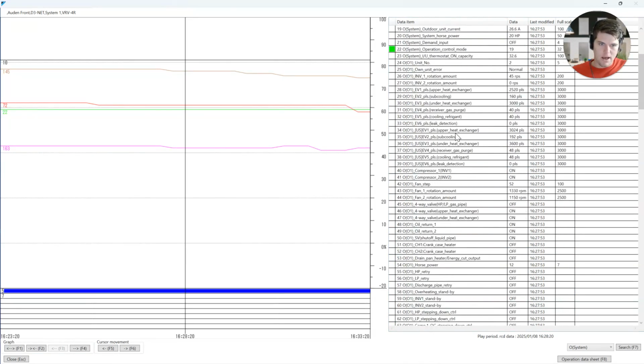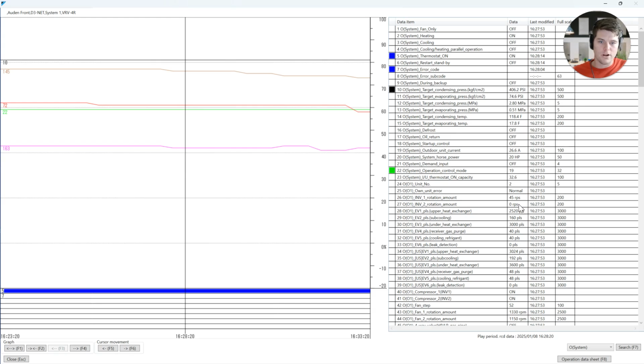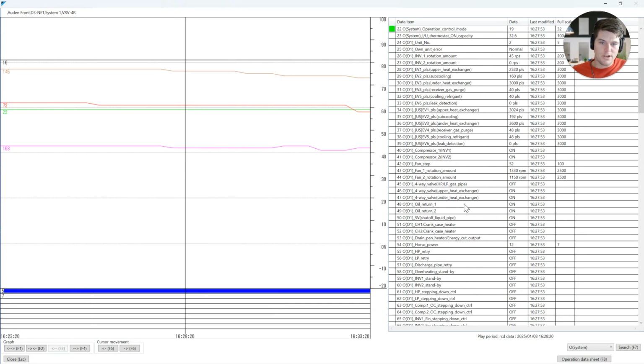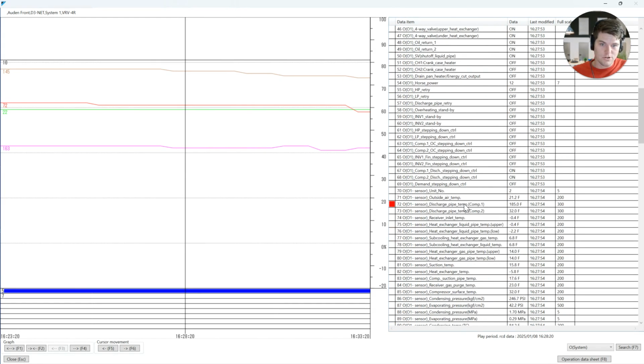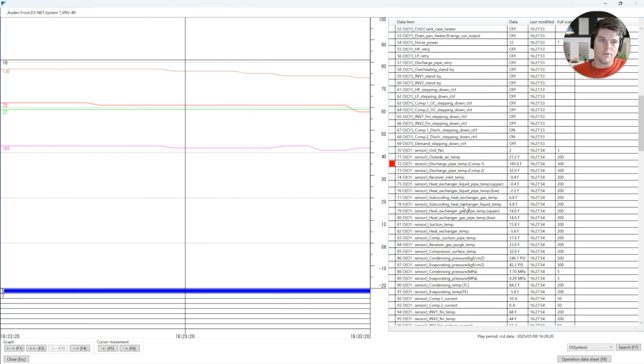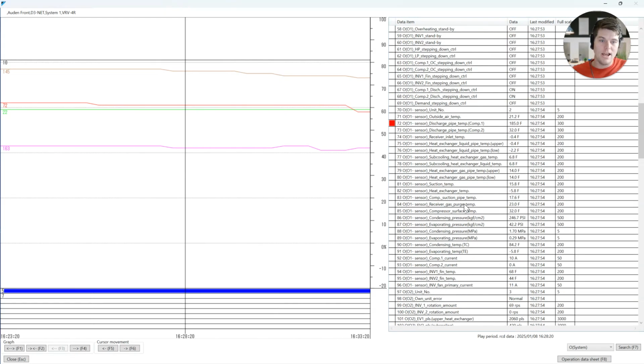Why does discharge superheat matter? It tells us the quality of compression within a compressor. If I know that my suction superheat is good, I'm getting a 10-degree suction superheat, I'm getting 100% vapor of the right volume back to my compressor, but yet my discharge superheat is high. It's higher than 72. That range is 32 to 72, which we talk about in the 3 pillars video. If it's above 72, the difference between good vapor coming in at 100% quality into my compressor and high discharge superheat coming out of my compressor, the difference is a lack of oil. That's what science tells us. The difference is a lack of oil.